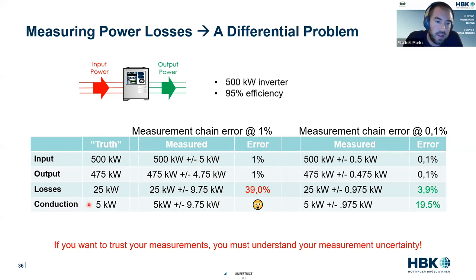And then we look at something like conduction losses, and it's just uncomputable. So if we move to something like a 0.1% error, well, now we've run the same math, but now we have a 3.9% differential. We can actually start to trust this measurement. So if you want to trust your measurements, you must know your measurement uncertainty. You must understand it. This is where HBK can offer some of that expertise.